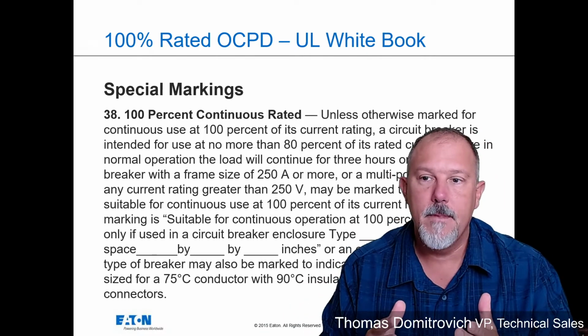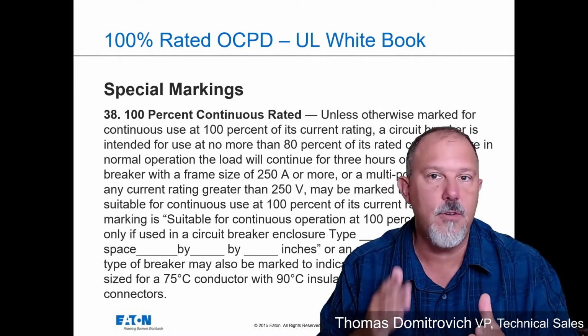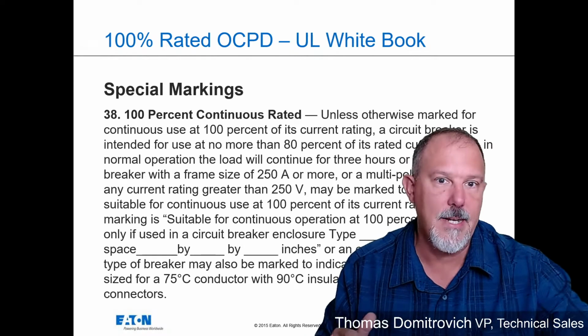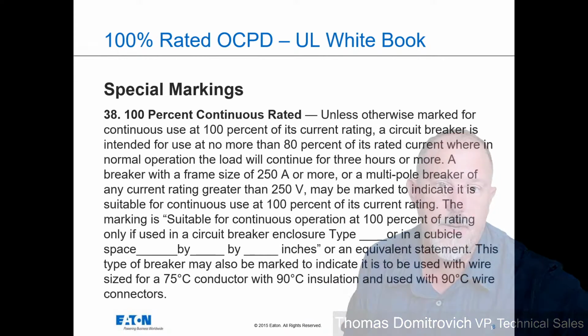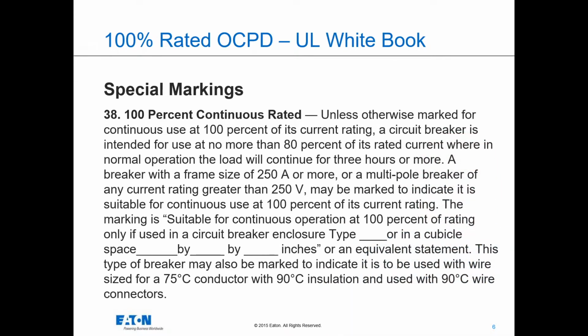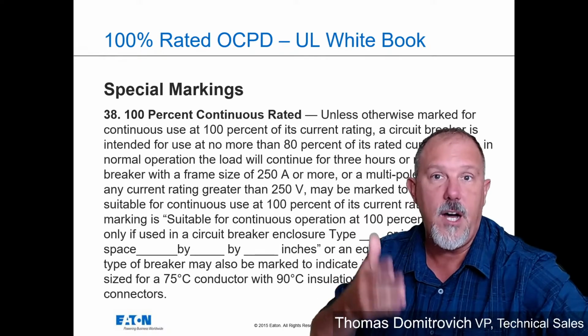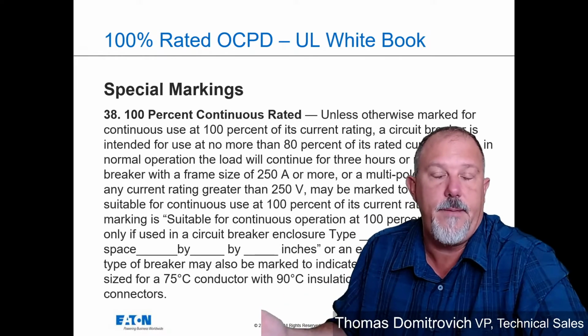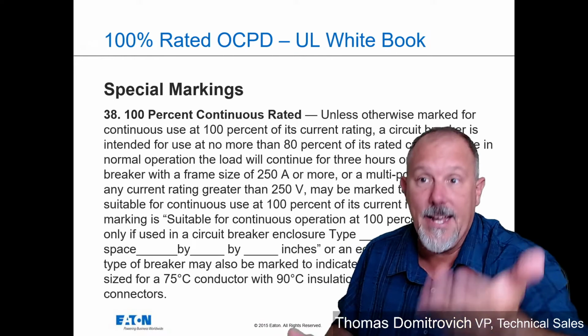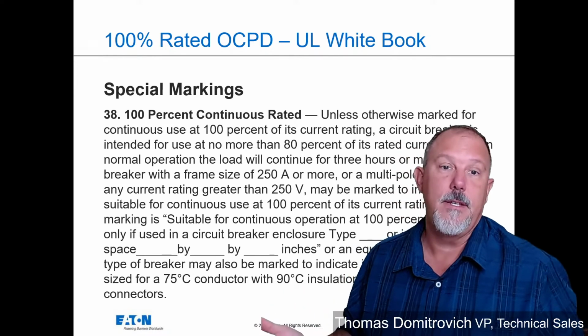So that's my issue. I think I don't need that to be 100% rated for this reason right here. It's 80% of its rating. So 1600 amps is 80% of the rating of that 2000 amp breaker. It's a 2000 amp frame breaker, so I can carry 80% continuously.